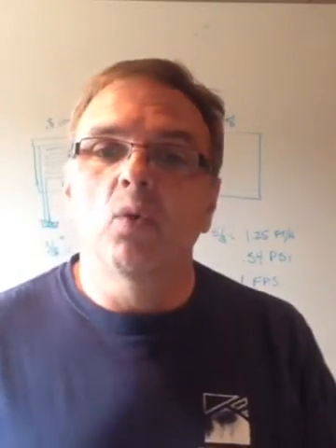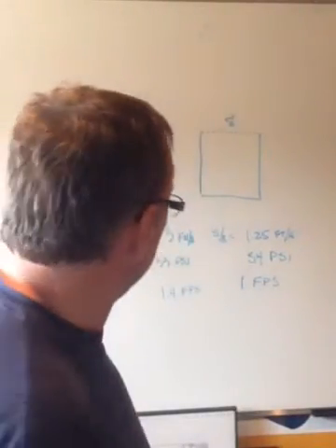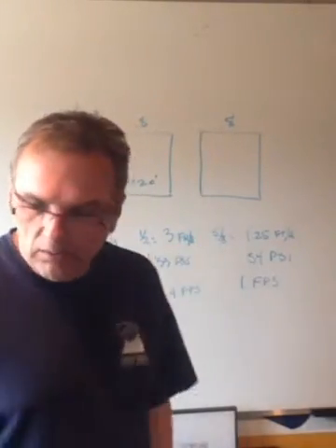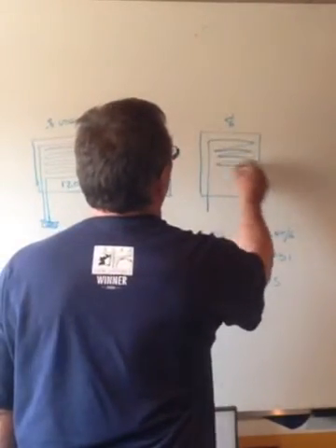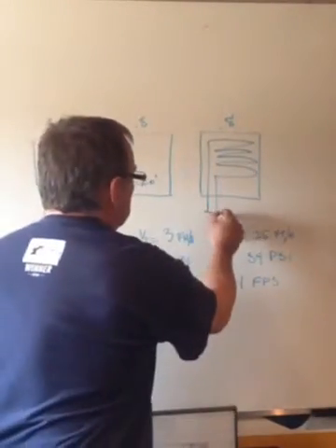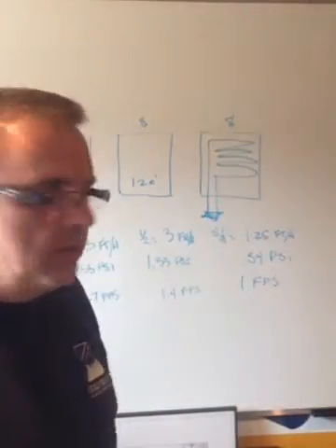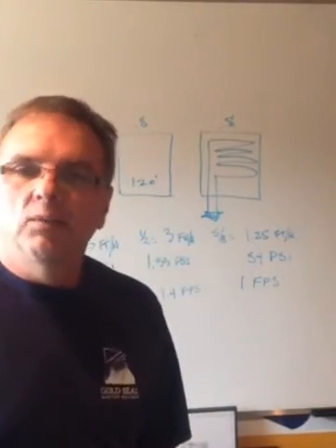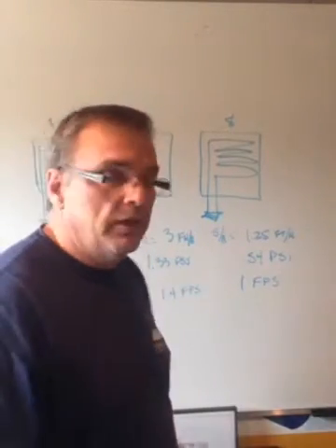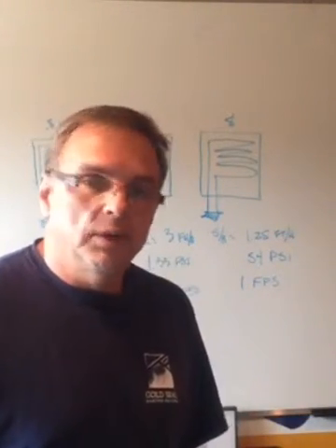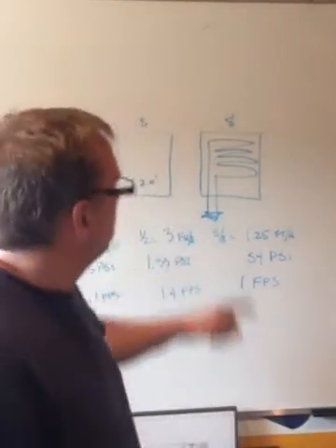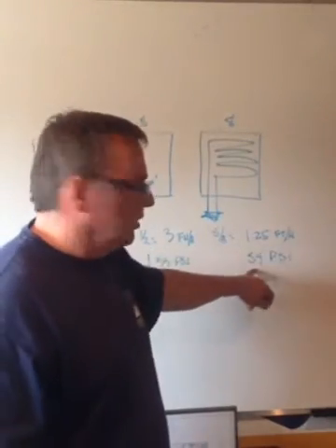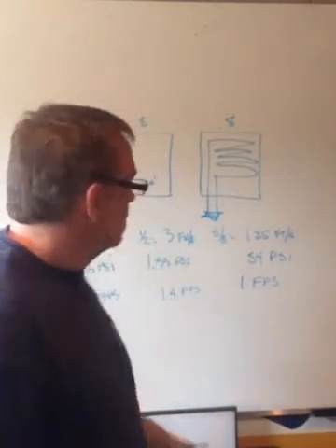Now in the old days, when I started 25 years ago, we had one size of pipe. It was 5/8 tubing. So we would install a loop in such a manner, doesn't really matter how right now, of 5/8 tubing, and then we do some math, and you can find this stuff on the internet and figure out what kind of flow rates we have. Well, not flow rates, but friction loss. The important thing about picking your pump is knowing, 1, the flow rate, and then 2, knowing the pressure drop in the loop, okay?